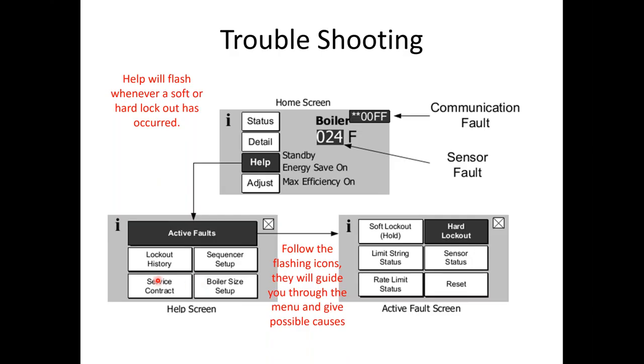Very, very straightforward. It's going to basically tell you what's going on with it. The sensor faults, it's going to either be 024, 728, or -512. All of those three numbers are basically telling you that that sensor has failed. Usually it's 024 or -512. If it says 728 degrees, it is usually shorted. Something bad happened there. But the help button will be flashing. If you press help, it'll go into active faults. It'll be soft lockout, hard lockout, limit string, and it'll kind of tell you what's going on with it.